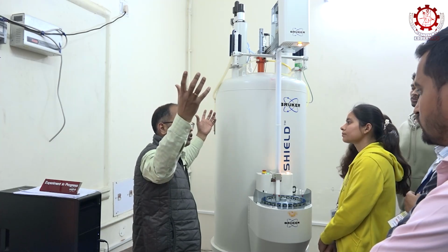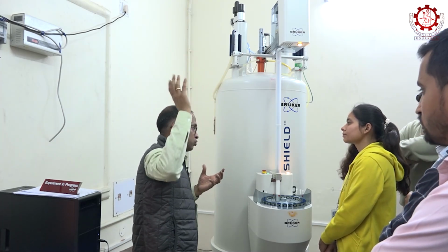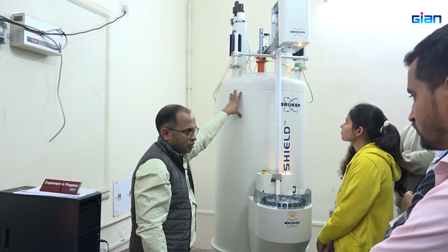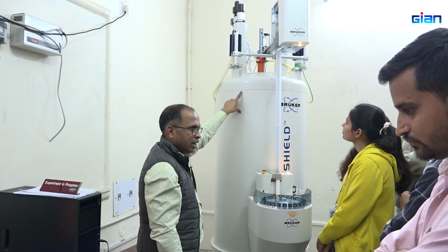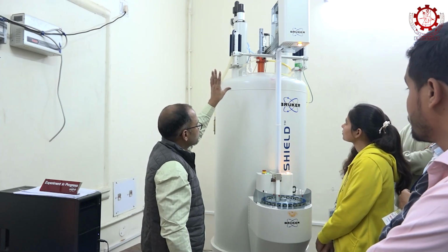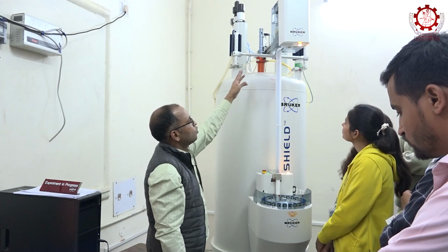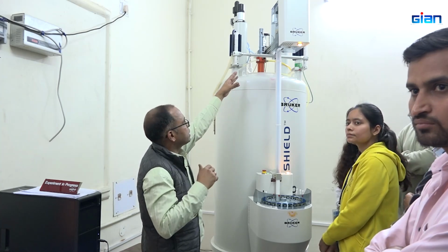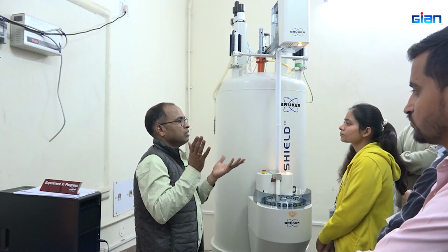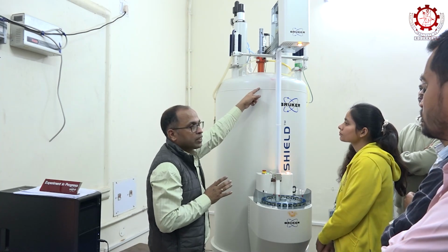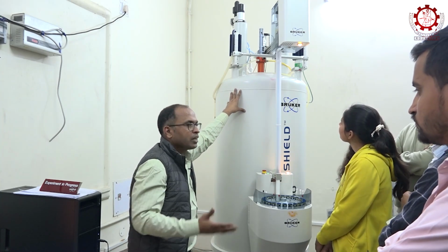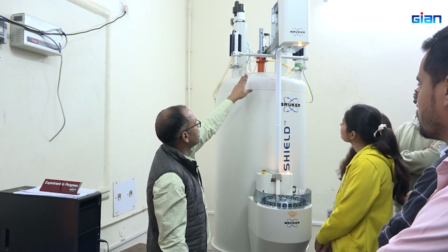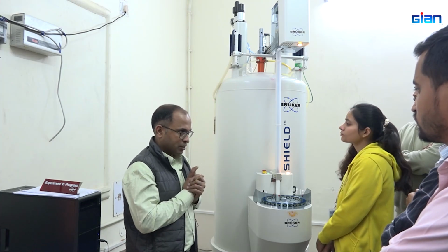So what we do, we just liquefy the nitrogen gas. That is cheap, but helium we don't have, so that's why helium is pretty expensive. We fill liquid helium, and to slow down the evaporation of helium, we put nitrogen. And Subhadeep can tell you, this liquid helium we fill once in 6-7 months, but this liquid nitrogen we fill every week. And again, that is cheap, so we can afford that. So that is there, liquid nitrogen, then liquid helium, then inside you have the magnet.